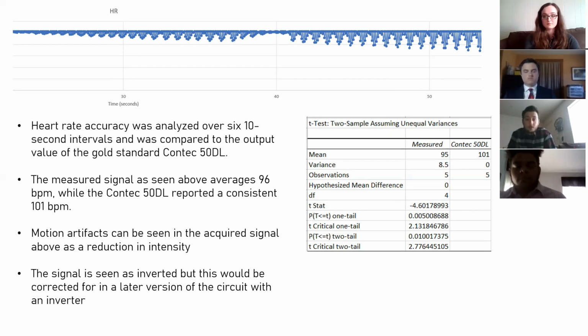The sensor output was compared over 6 10-second intervals to the gold standard, the Contec 50DL optical finger heart rate monitor, and the design sensor showed an output of 96 beats per minute, while the Contec sensor showed a consistent 101 beats per minute, leading to an overall error of 4.9% or an accuracy of 95%. And unfortunately, due to an infrared LED burning out in testing, no data can be collected for pulse oximetry at this time.